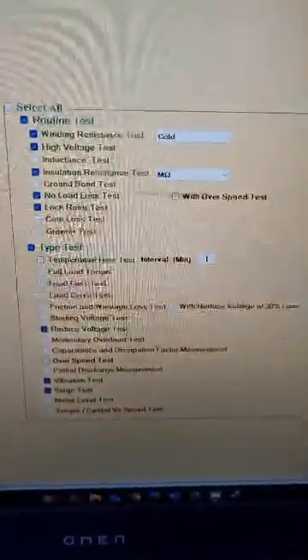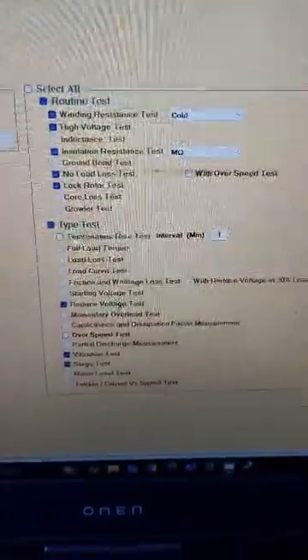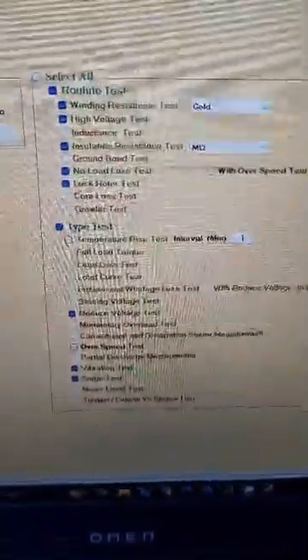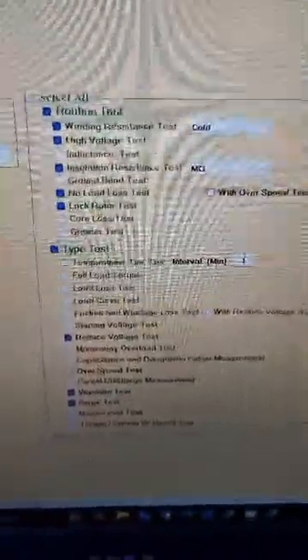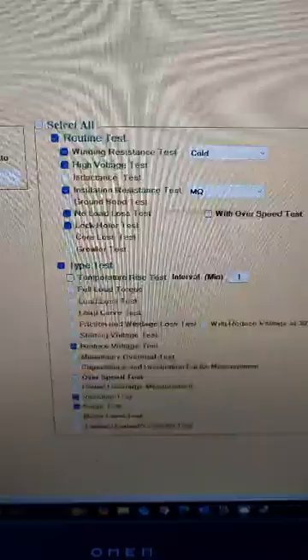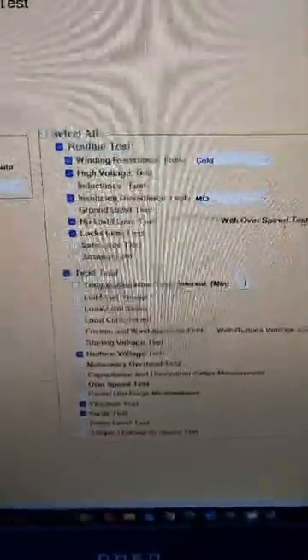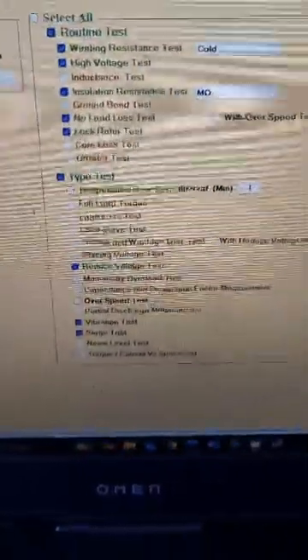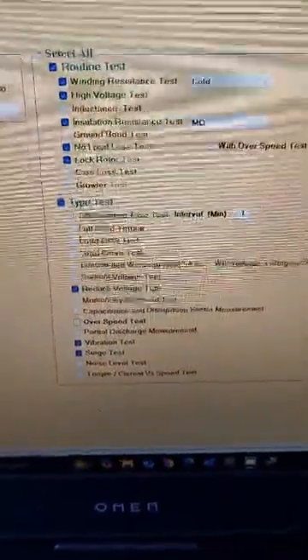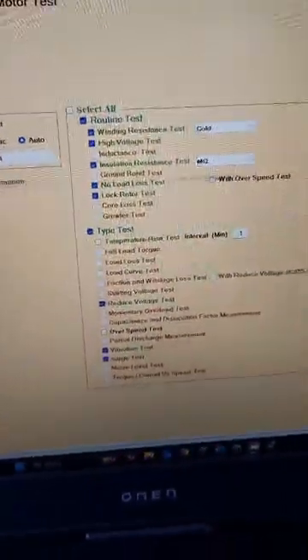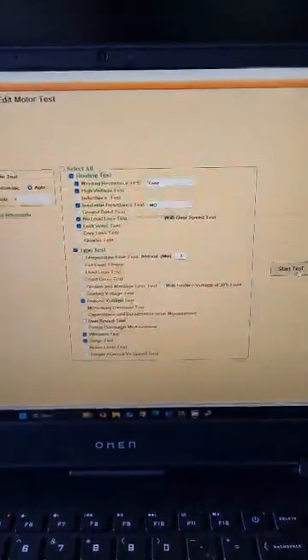You can see the routine test selected to be conducted automatically, or winding resistance test, obviously in cold condition. This is the no load test setup, high voltage test, the insulation resistance test, the no load test, the lock rotor test, the temperature rise test on no load, the reduced voltage test, the vibration test, the surge test. These were required by this particular customer for whom this test bench has been built.